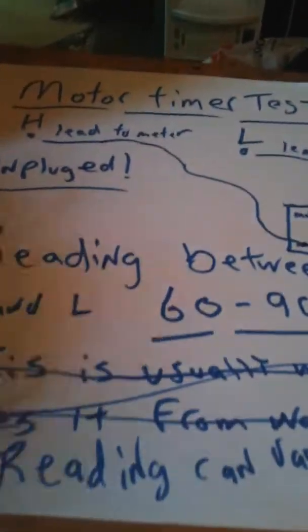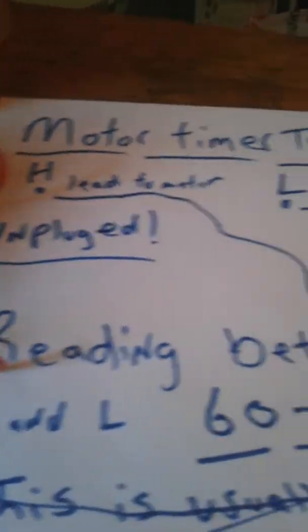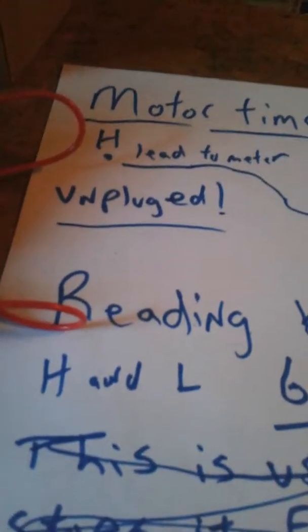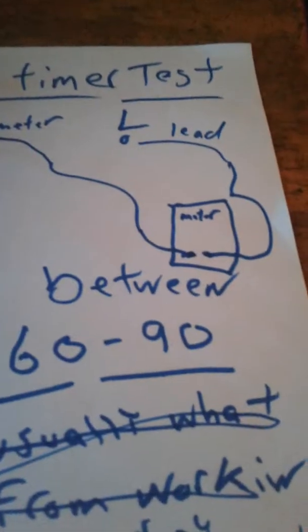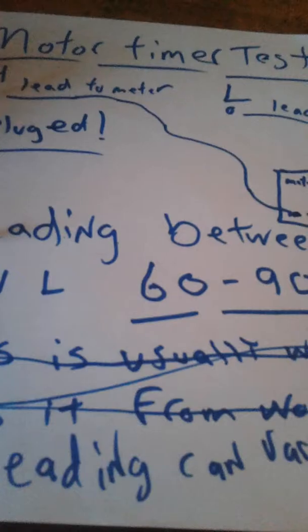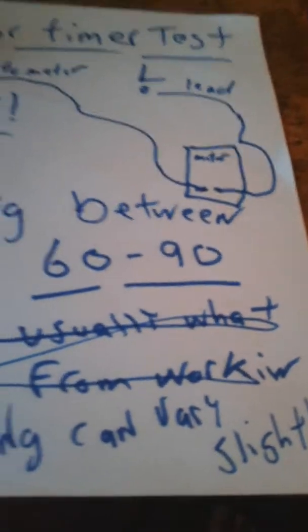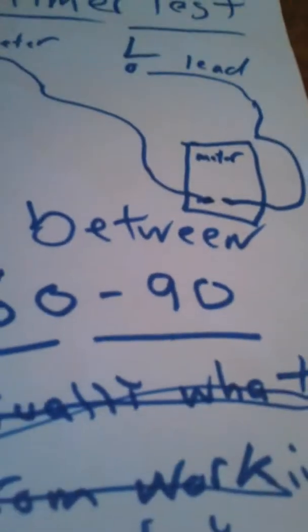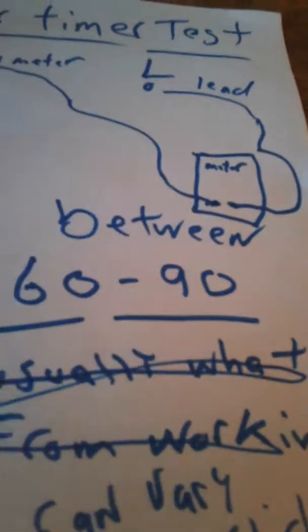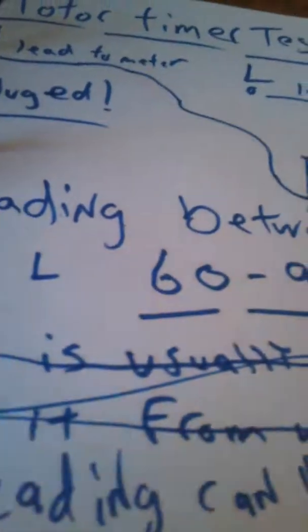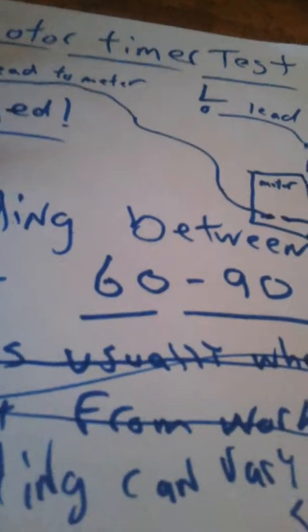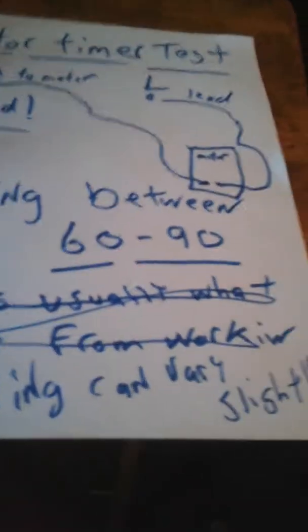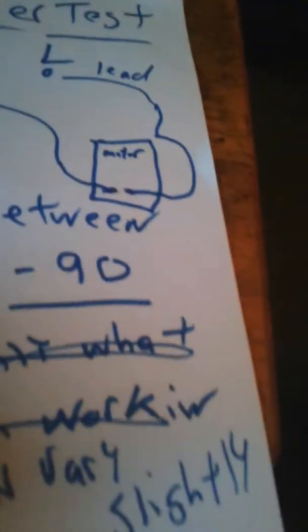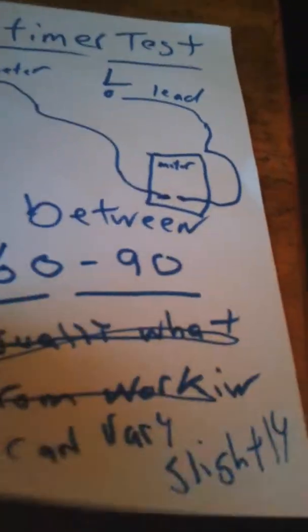This is for the motor timer test. H lead, L lead. You should have between 60 and 90 show up on the face of your meter. If it's maybe 5 over 90 or 5 below 60, that's okay, but anything more than that, your timer's bad. This is what usually goes wrong. All right, we're going to go on to the next.